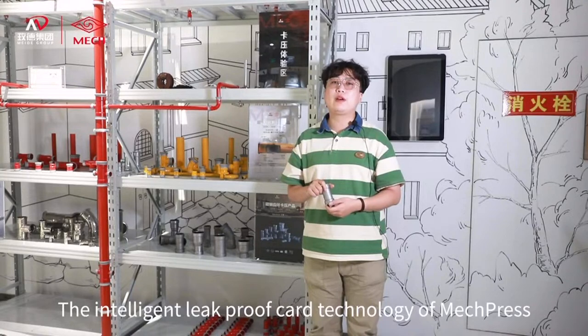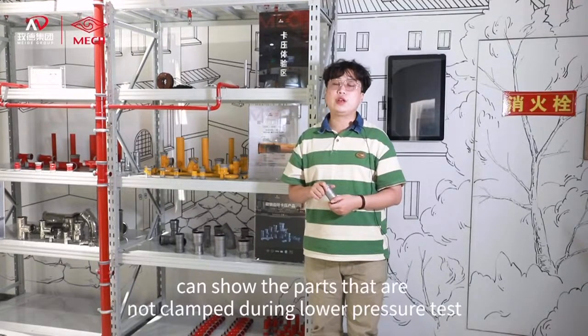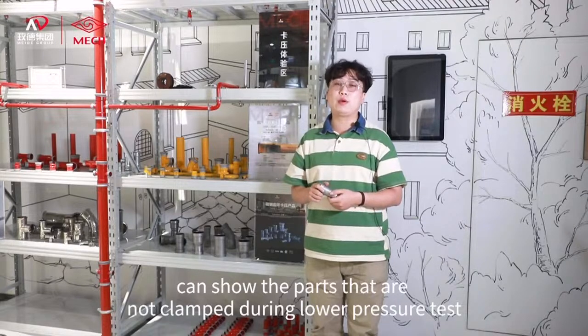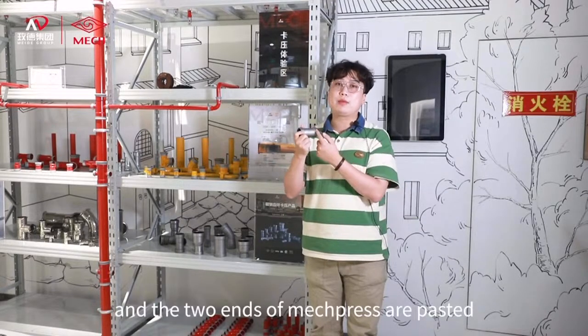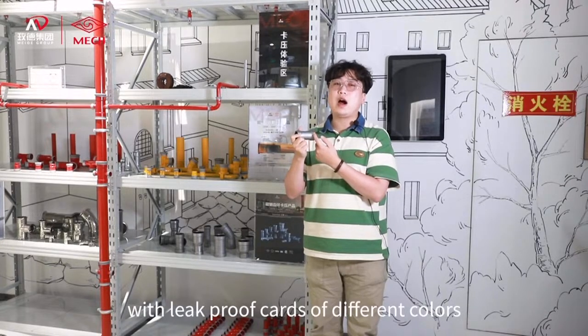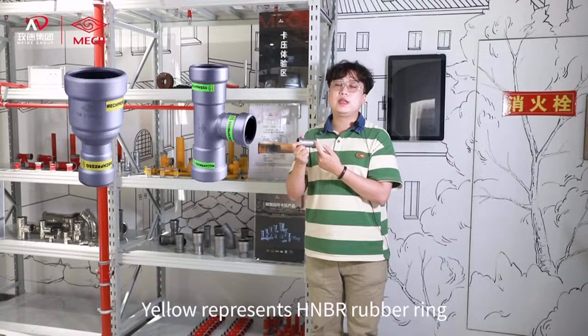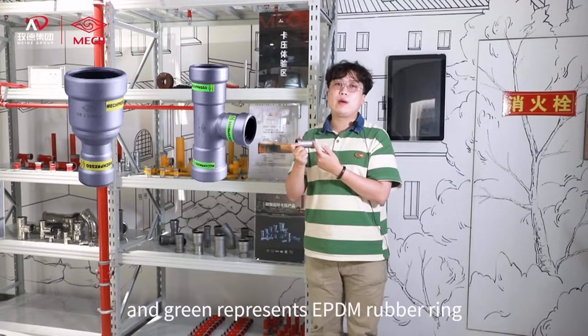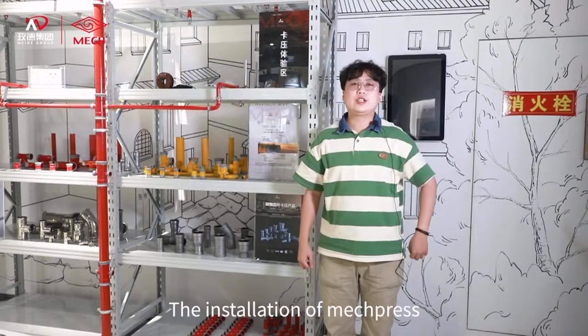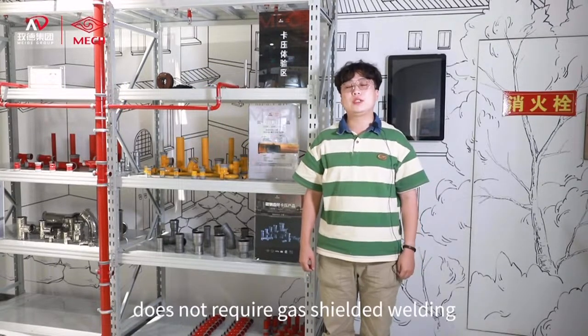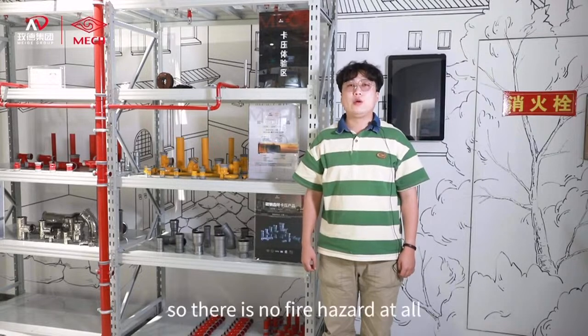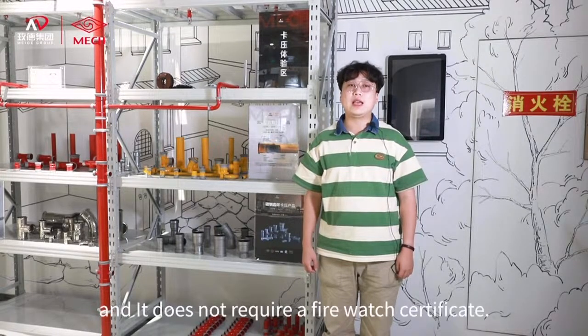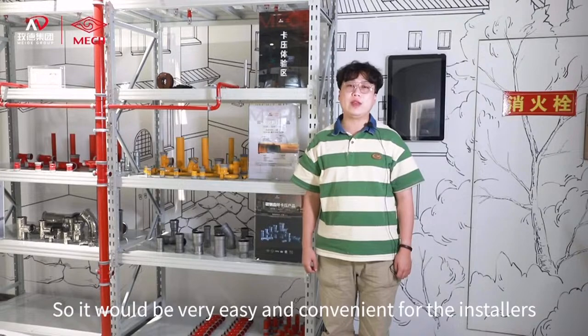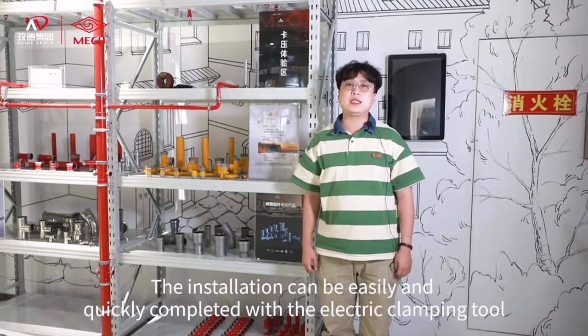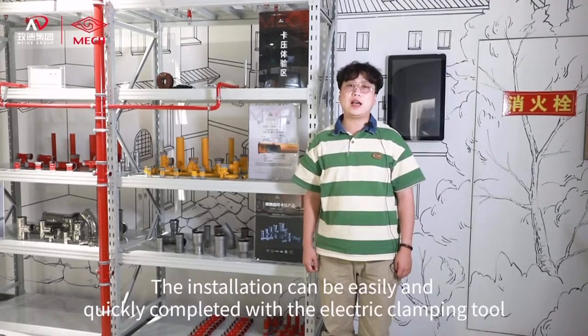The intelligent leak-proof card technology of MechPress can show the parts that are not clamped during the low pressure test. The two ends of MechPress are pasted with leak-proof cards of different colors. Yellow represents HNBR rubber ring and green represents EPDM rubber ring. The installation of MechPress does not require gas-shielded welding, braiding, and threading, so there is no fire hazard at all, and it doesn't require a fire watch certificate, so it is very easy and convenient for the installers. The installation can be easily and quickly completed with just the electric clamping tool.